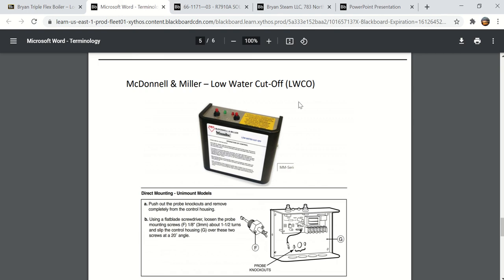But that is the probe type low water cutoff. Anytime you see the initials LWCO, you should think low water cutoff. When it says probe type electronic, that's exactly what you're looking for.